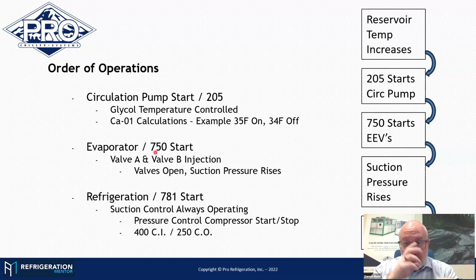The 781 is what's driving that signal to those VFDs, saying, how much compressor capacity do I need? That is based off of my suction temperature requirement, not my suction pressure, which is just a cut in, cut out. My actual ramp up and ramp down of capacity is dictated by my actual suction temperature. So evaporator's on, valves are moving, suction pressure comes up, I hit 400 PSI, my compressor starts. If my suction pressure drops down to 250, that's my cutout point. I shut my compressors off.